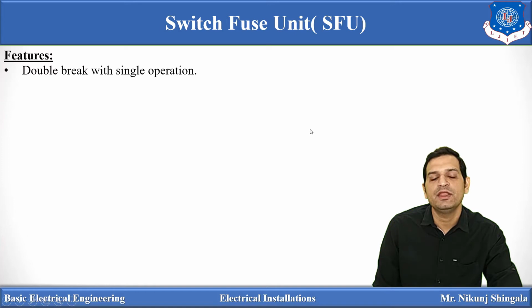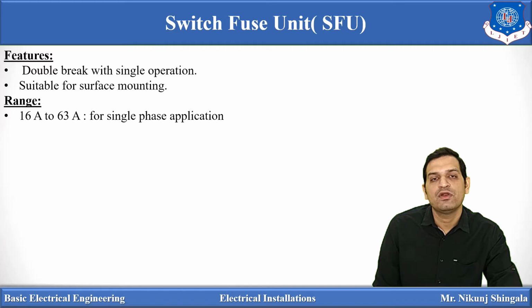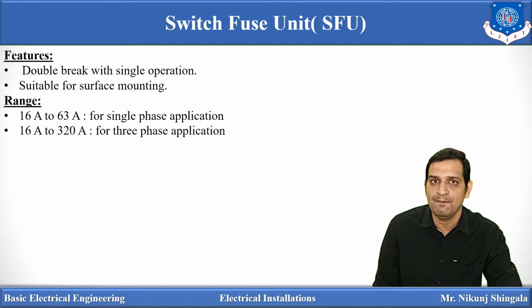Now, which are the features of the switch fuse unit? It provides double break operation with a single operation. It is suitable for surface mounting. Range, that is the capacity: for single phase application it works from 16 ampere to 63 ampere. For three phase application it works from 16 ampere to 320 ampere.